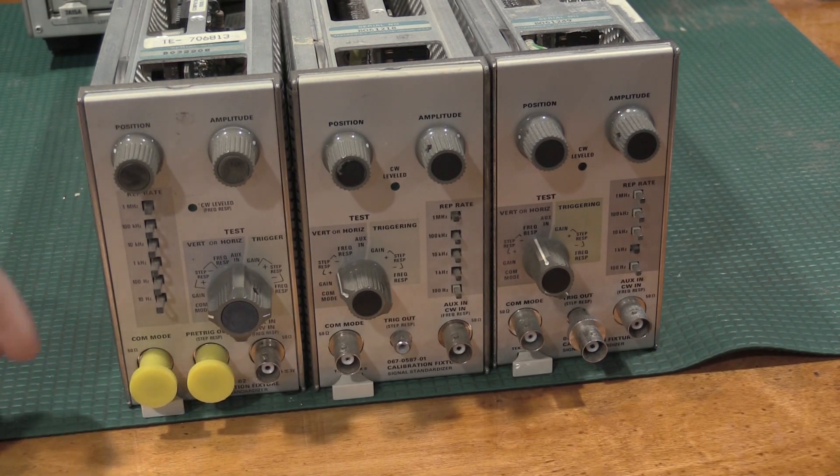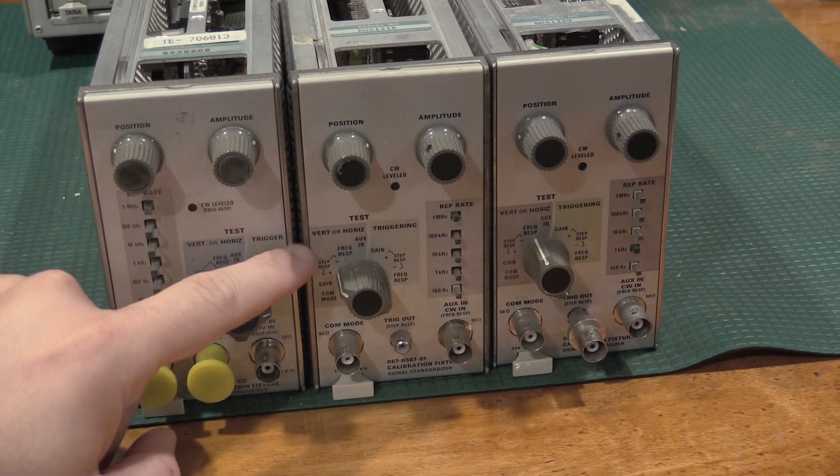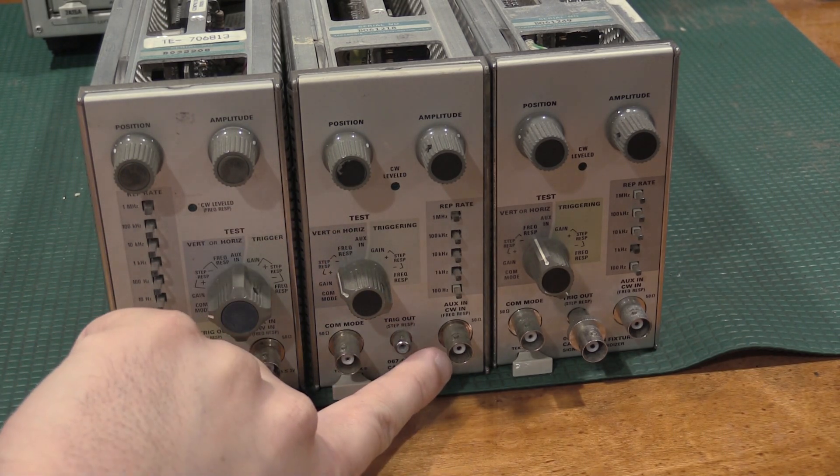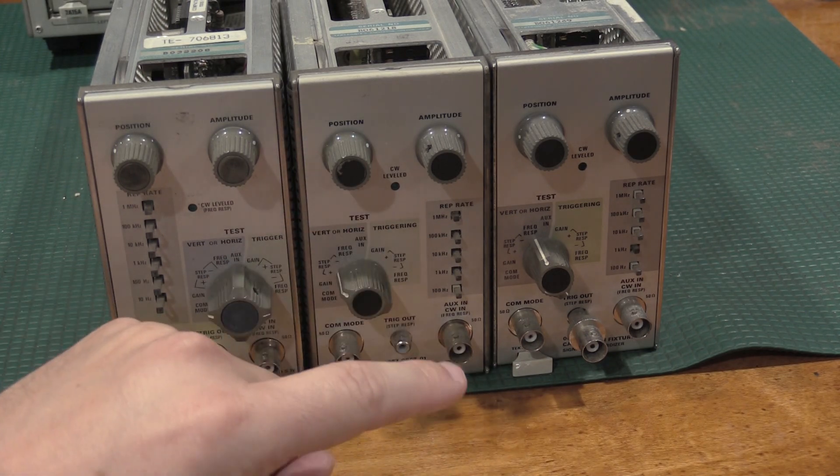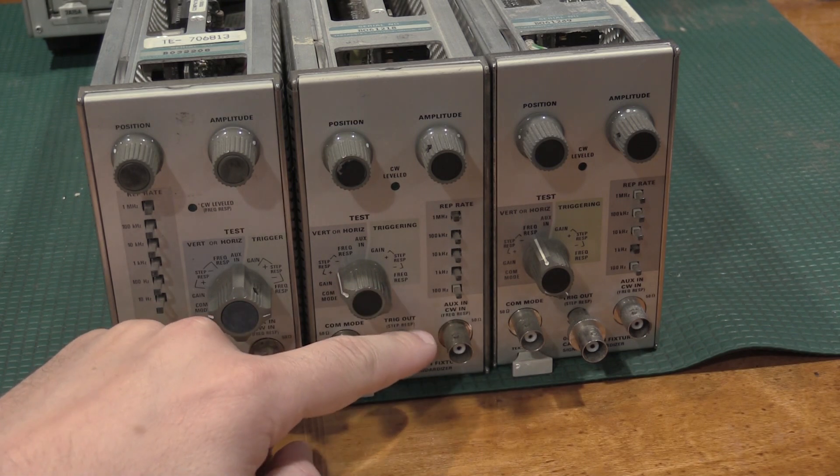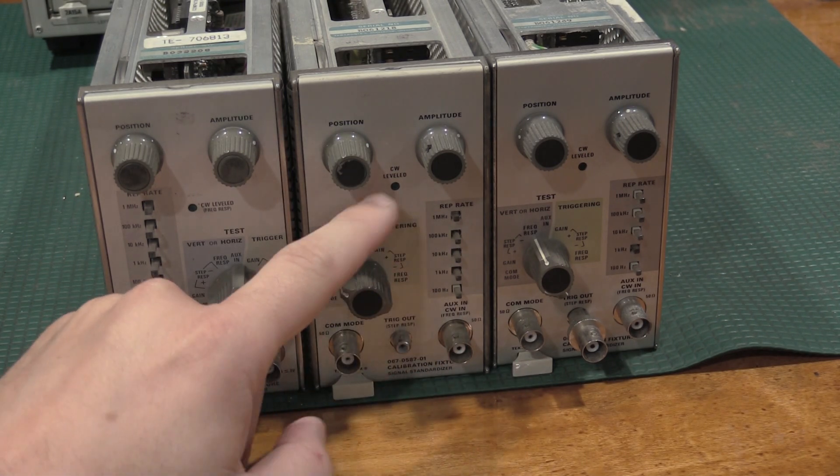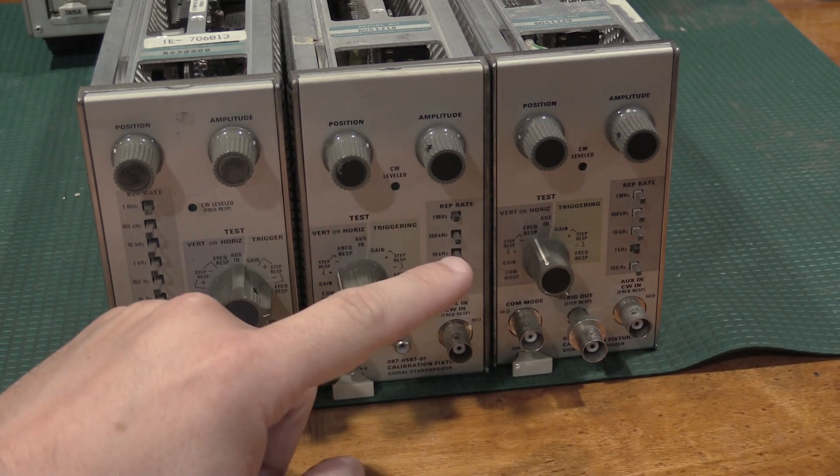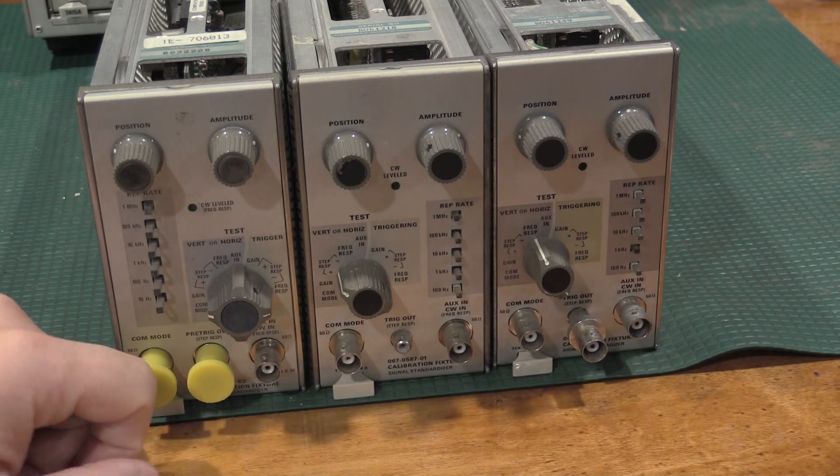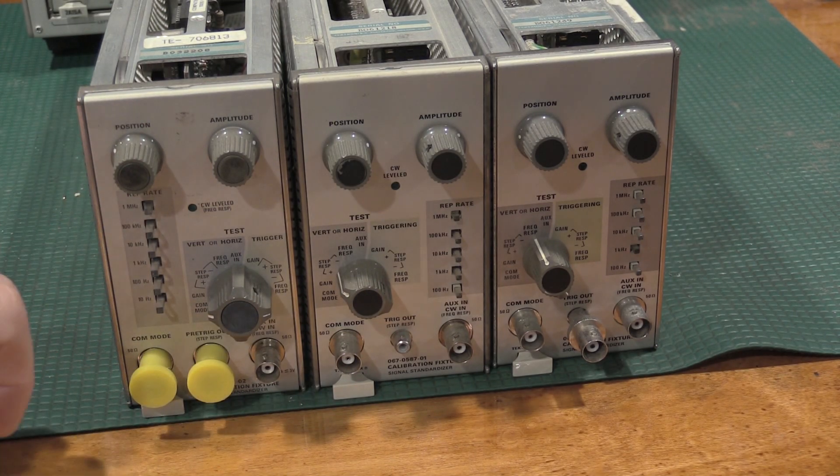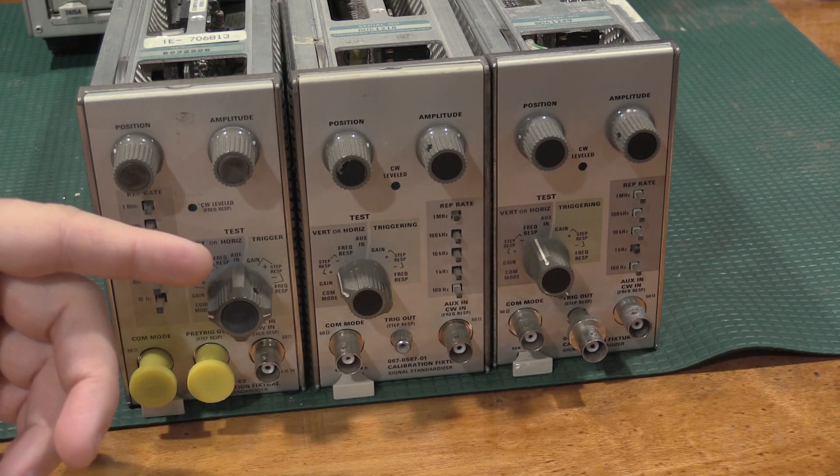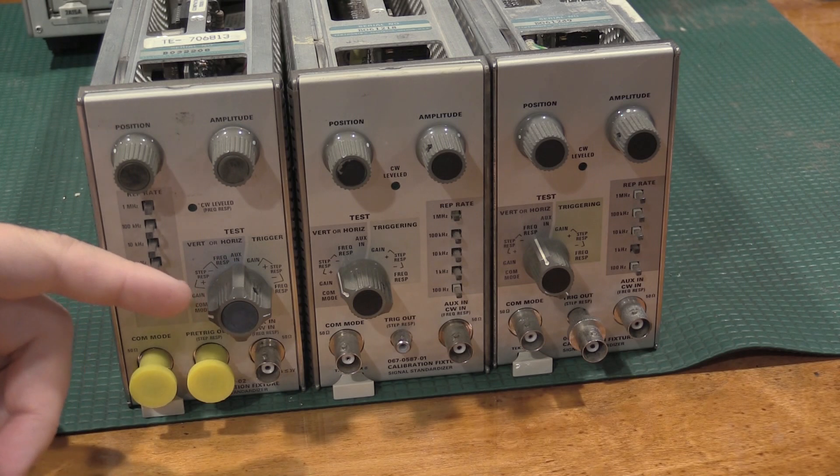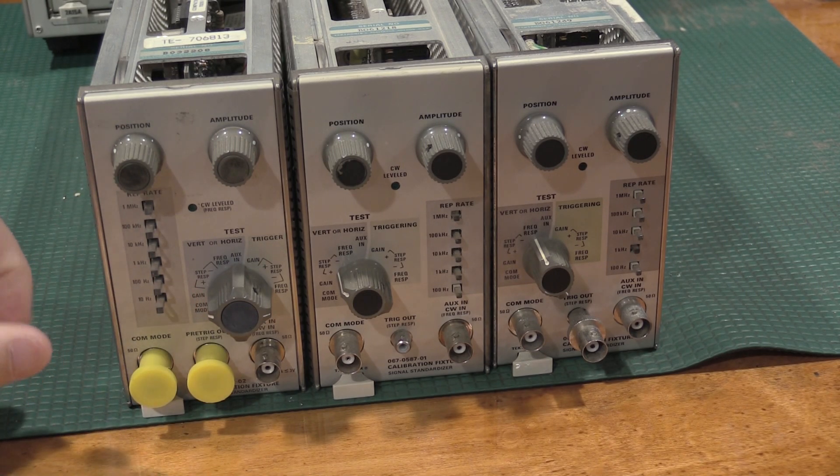And the only difference between the dash 01 and the dash 00 is the rep rates. This has faster rep rates and faster edges. The other thing that's really important on this is when you do the frequency response of the vertical or horizontal ports, this actually does the leveling feature. So you plumb a SG503 or an SG504 into here, and this does the leveling. CW is carrier wave leveled. And this makes sure you can do the bandwidth check on the port itself without a vertical plugin in the way. So you're getting the full bandwidth of the port in the frame, not taking into account the vertical bandwidth of the 7A plugin that you might be using.